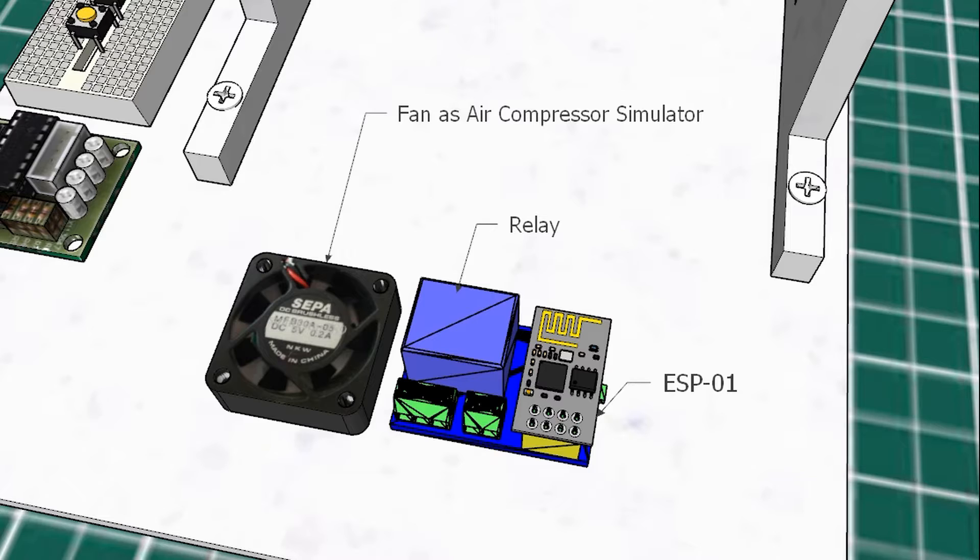After getting pressure value, it will turn on or turn off the relay based on value. If pressure drops, it will turn on the air compressor. If pressure reaches the maximum, it will turn off the air compressor.